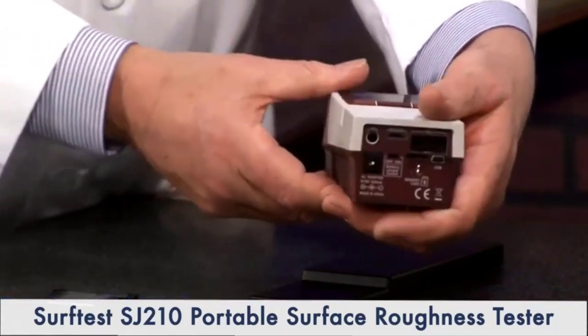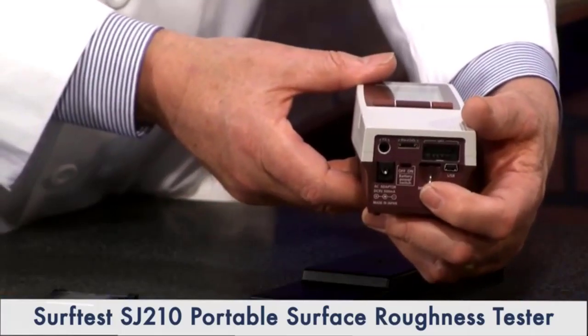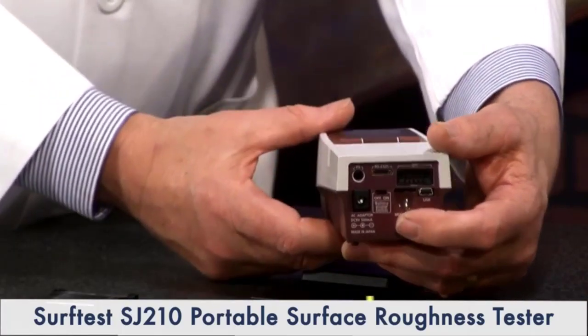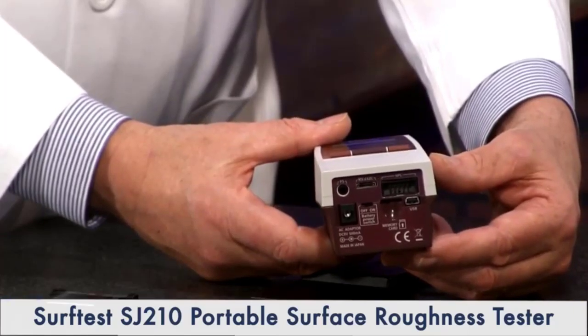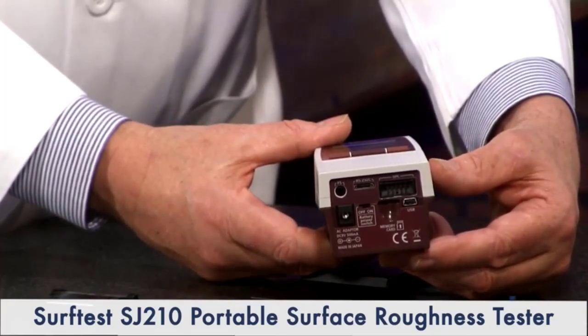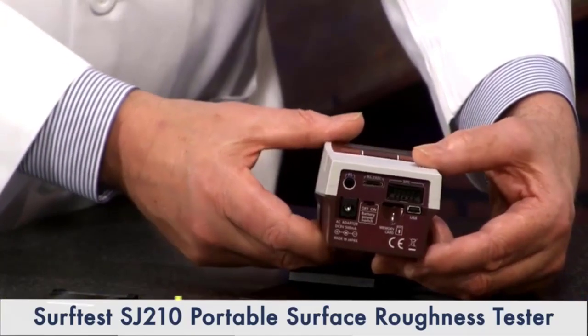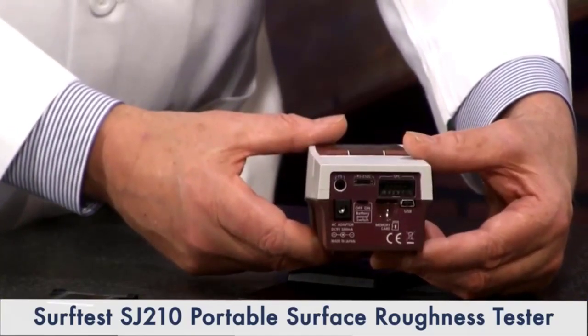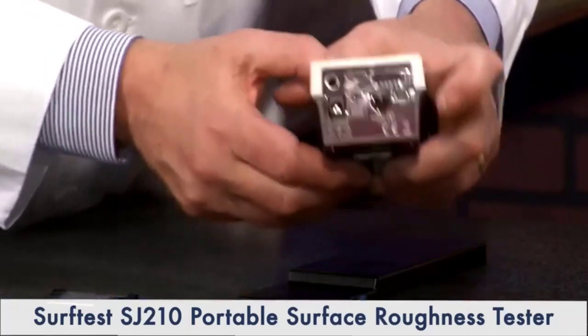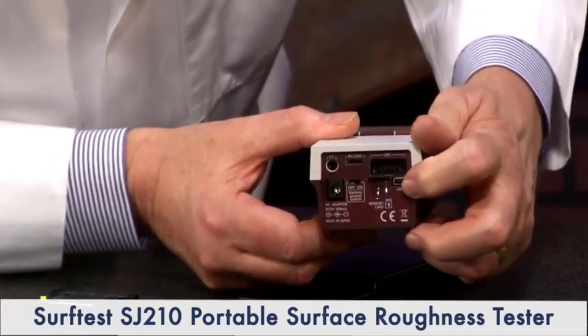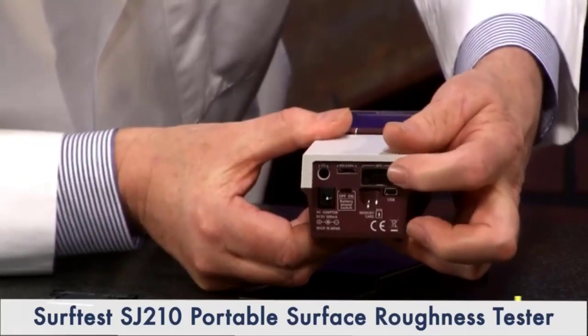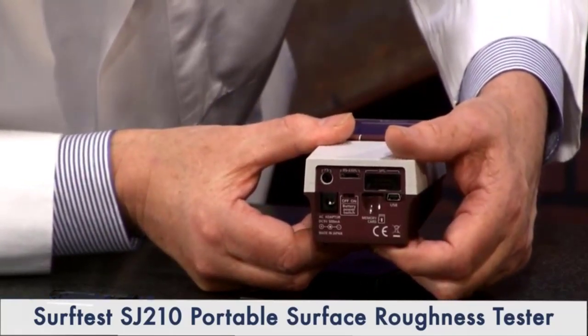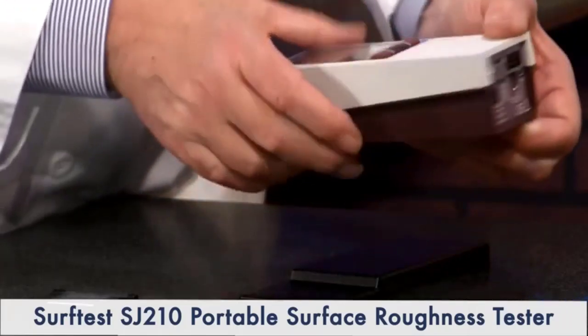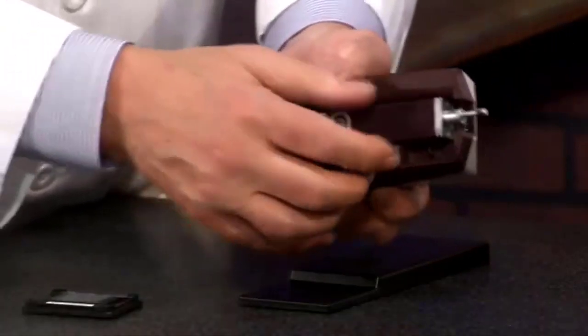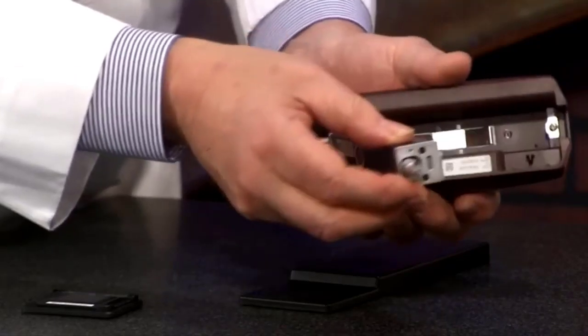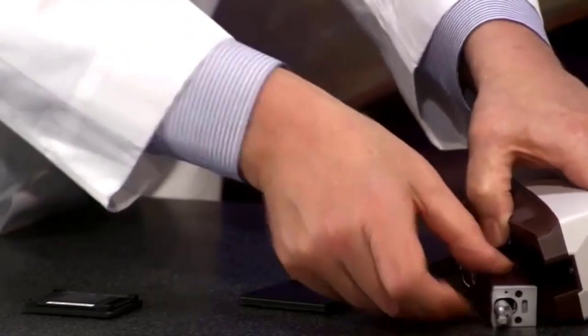On the back end, you can have a memory slot for an SD card. As it comes, it'll store 10,000 results. It'll store 10 measurement conditions and 1 measurement profile. But for some people, that's just not enough. So it has USB. We've got a USB output. It has SPC output for going right into spreadsheets, that sort of thing. Very versatile instrument.